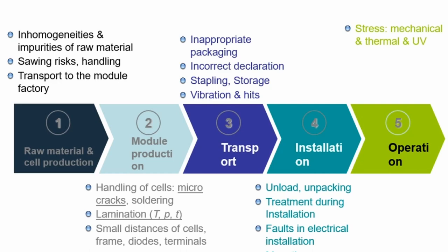During operation, stress can come from mechanical, thermal, and UV sources depending on location. For example, in the desert, large temperature differences between day and night create extraordinary stress. We recently carried out tests in Bolivia where modules are installed above 4000 meters above sea level, resulting in extraordinarily high UV stress. Finally, hot spots and PID are important issues — PID, micro cracks, and lamination will be discussed in more detail.